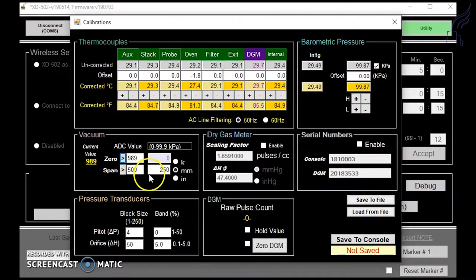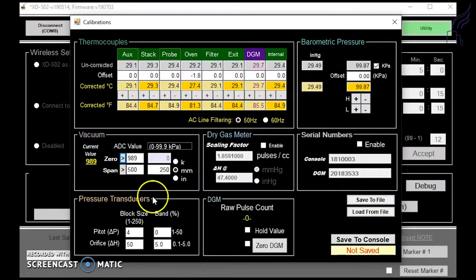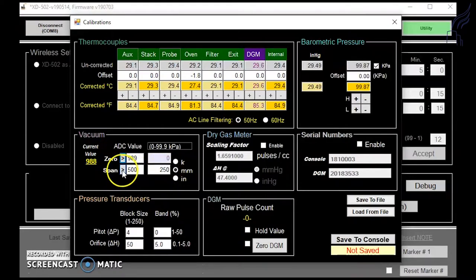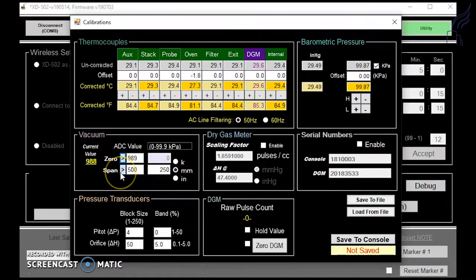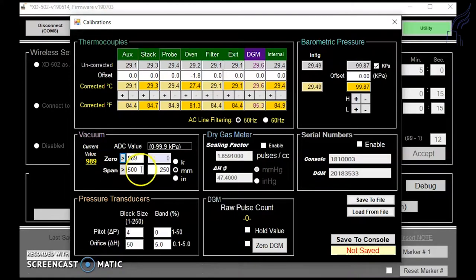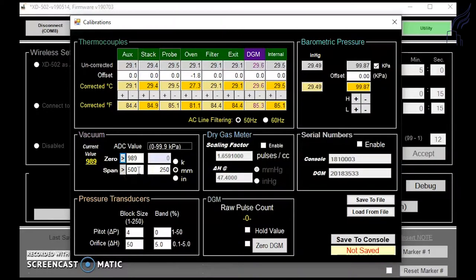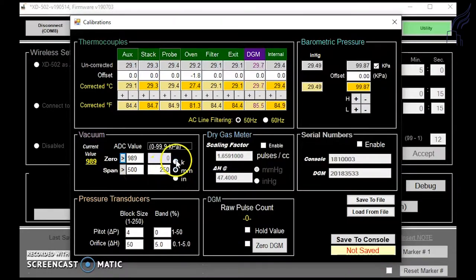You'll then input the number on your reference vacuum gauge inside the box here and capture the value by clicking on the arrow here. This will capture your maximum vacuum value so you can get an accurate reading at your maximum level. You can change the units by clicking on the tab here as well.